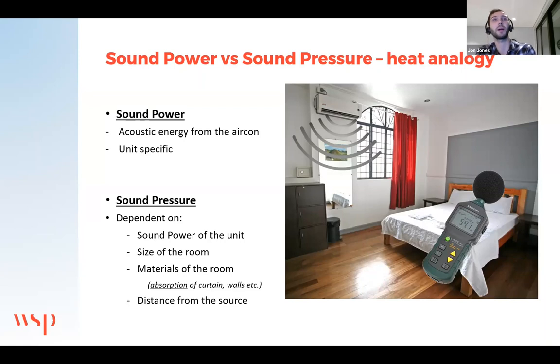difference. You still have the sound power, which is the total energy contained within that specific unit, and the sound pressure level is then dependent on the sound power level, which is your input energy from the unit, but is also affected by the size and all the materials of the room. In the heating analogy, you might have absorptive materials that absorb heat or reflective materials. You have the same thing with sound. So curtains, soft furnishings, etc., will absorb some sound and reduce the sound pressure level, whereas a very hard surface room will reflect the sound and increase the noise level within the room.